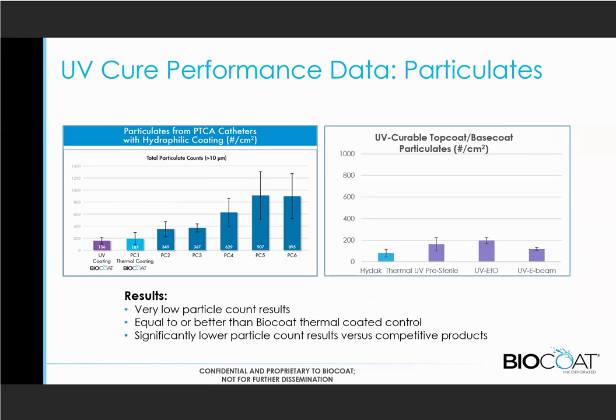And you can see there that, again, our thermal coating matched up nicely with what we had with the neurovascular. The UV coating also has a very comparable amount of particles generated, on the low end. Since this is a new product, we want to assure people about the sterilization effect. You can see on the graph on the right the thermal system, weighing into particles there. But then there are 3 from our HYDAK UV: one pre-sterile, and then also after ETO sterilization and even E-beam sterilization, to give people options. And really there's no change; we can see that particles stay pretty consistent over those two different sterilization systems.